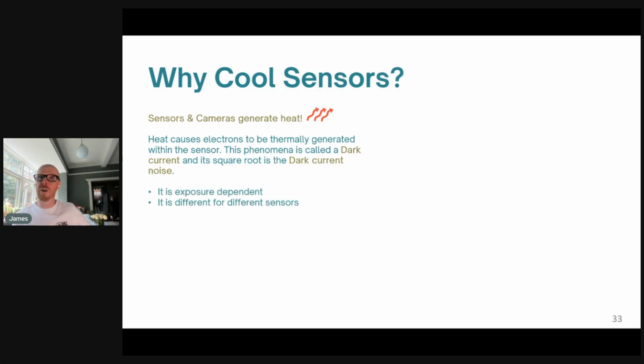This is exposure time dependent, and it's different for different sensors. So if your camera is cooled by -50, well done, congratulations - you could get a camera cooled by nothing and achieve the same dark current, because it's all down to the sensor. Dark current halves for every 7 degrees of cooling - sometimes. There are general rules, but it's not always the same. It doesn't always work; sensors are different. So that's the first thing.